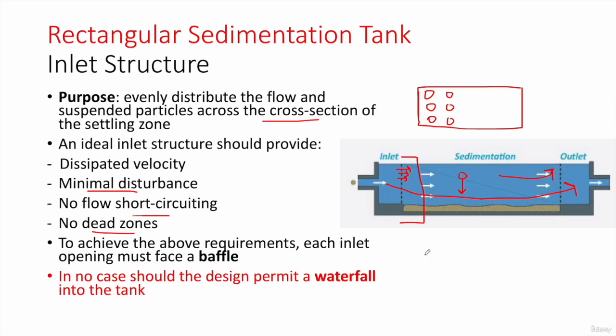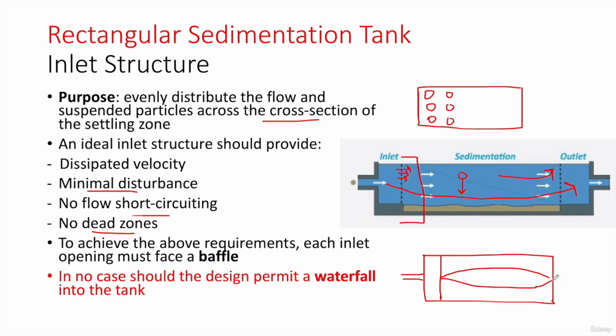A well-designed inlet structure also limits dead zones. For example, in the top view of the rectangular sedimentation tank, if the inlet is badly designed, the flow will only pass through one limited zone and dead zones will form in the hatched areas. No sedimentation takes place in these areas, making them useless, and the overall sedimentation efficiency is lost because the effective retention time is lowered.